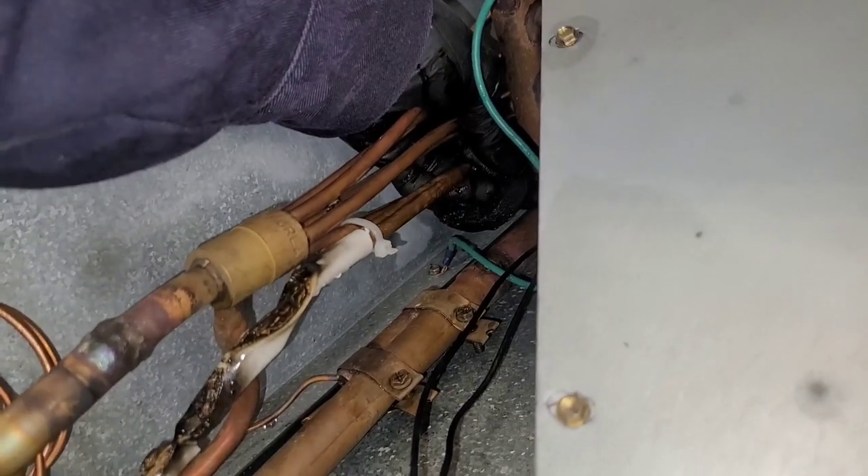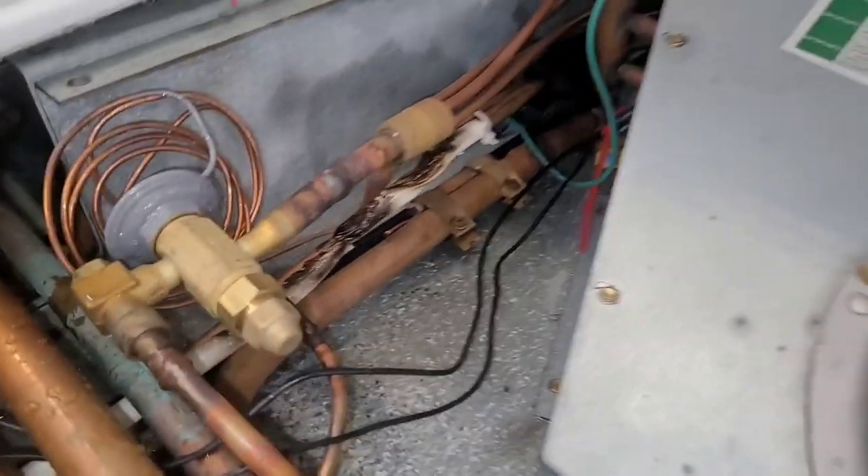This right here — I'm not sure what this is, but it looks like a wire. It could be a live wire, or most likely is a live wire. But to what? Where does that live wire go? Oh — that's a sensor, got to be a sensor. No, that's not it — okay, that's a sensing bulb for something. A sensing bulb for a temp controller that is not wired in. So this is of no concern — I can take it out of there if I want.